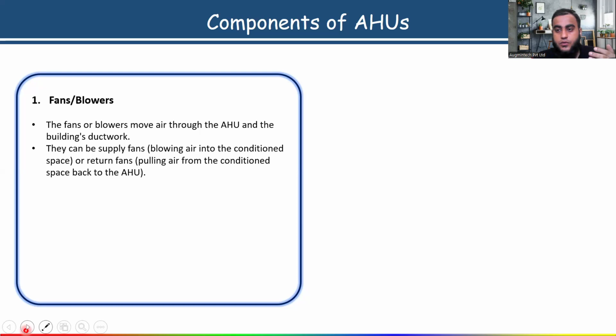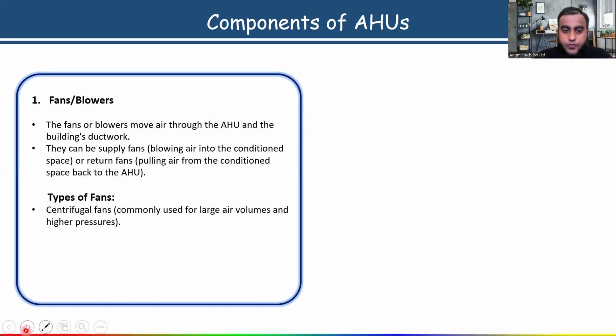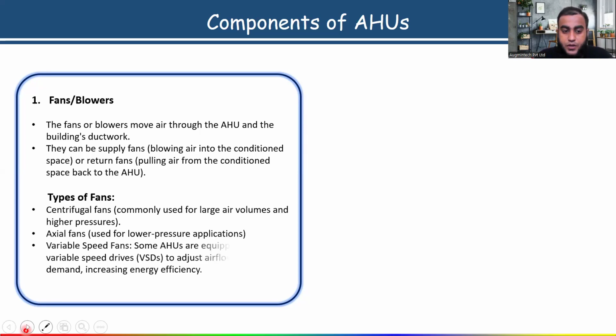So it depends on which type of area. If it is a large commercial area and you want to take the air back to the AHU, then generally we also use a return air fan. So different types of fans are there. Centrifugal fans are commonly used for large air volume and higher pressures, so you have to use the centrifugal fan. Axial fans are used for lower pressure applications, and variable speed fans we also use.